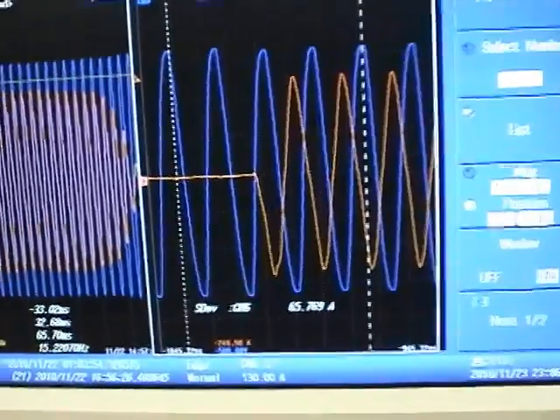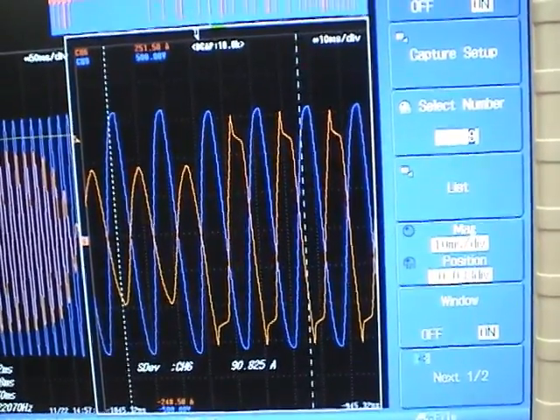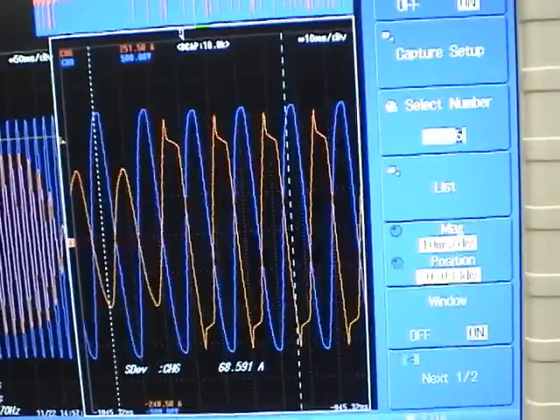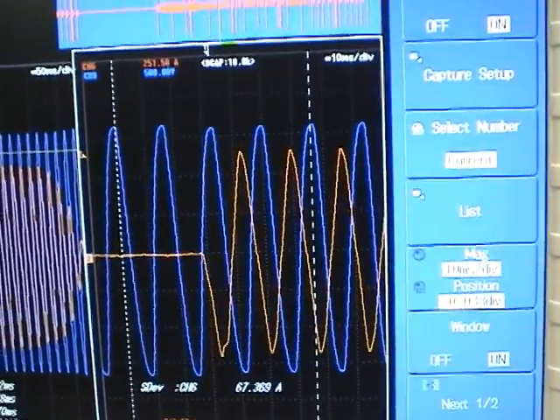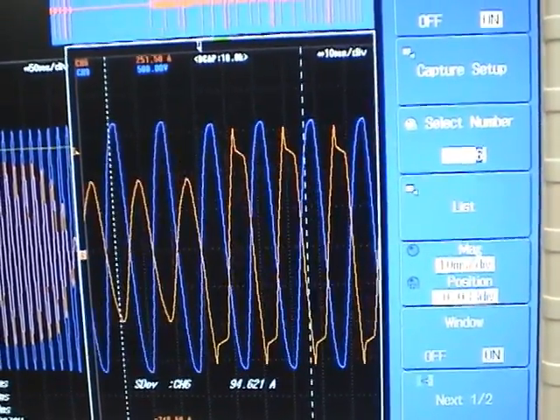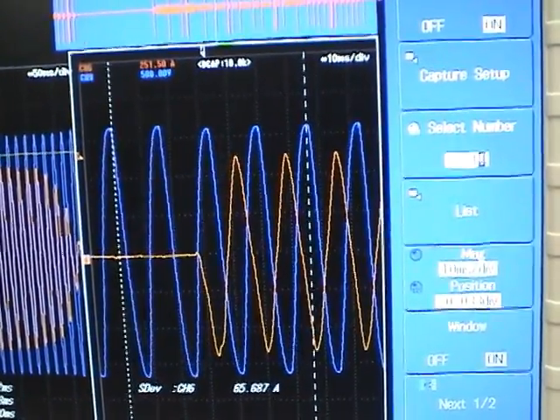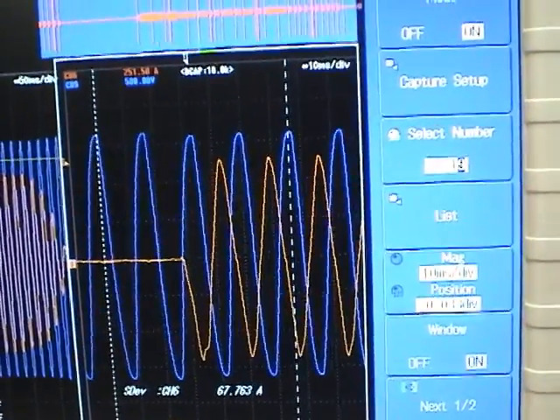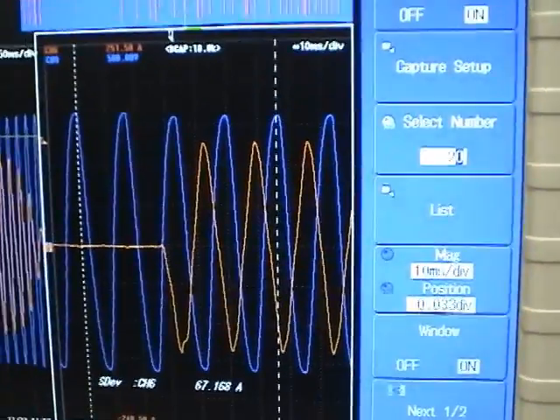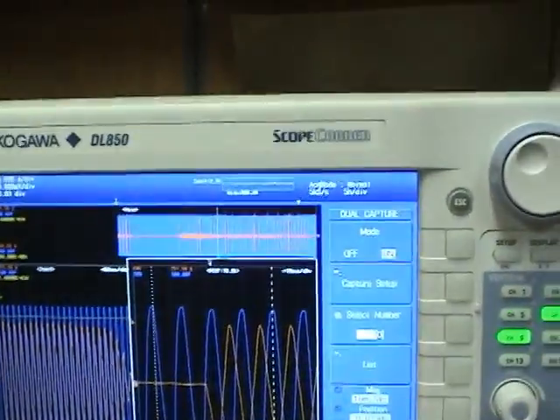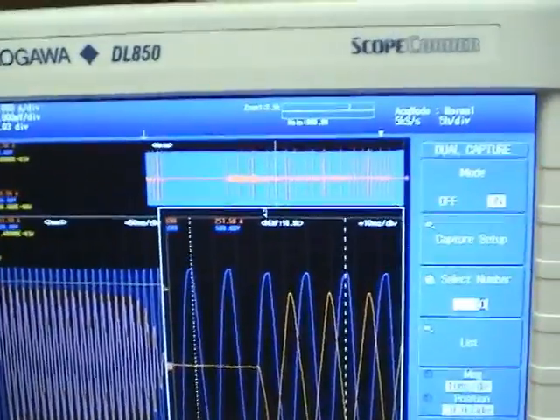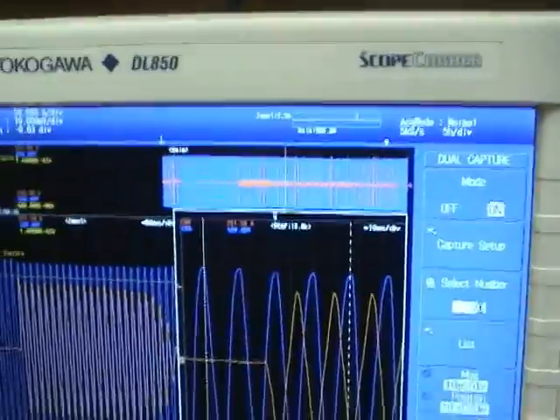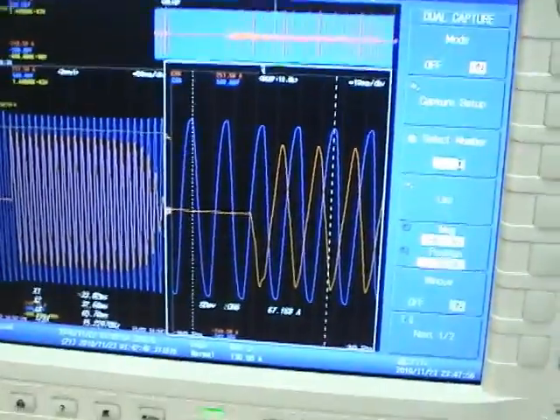I think we can see how the compressor contactor always turns on at zero crossing. So let's zoom in a little bit. Yes so now if we switch through them, it appears that the contactor always closes at zero crossings which I believe is what the heat pump manual, the control board manual says it does. And this is the type of application where a scope corder like this really comes into its own where you can record the very long duration relatively low sample rates and then sample certain events at high speed so you can see what's actually going on.